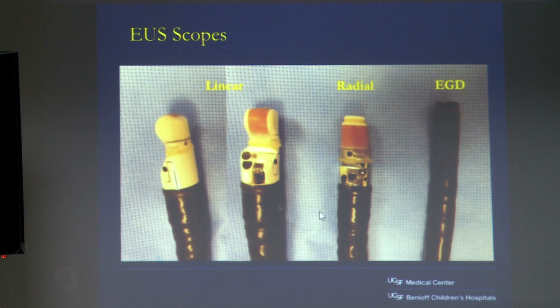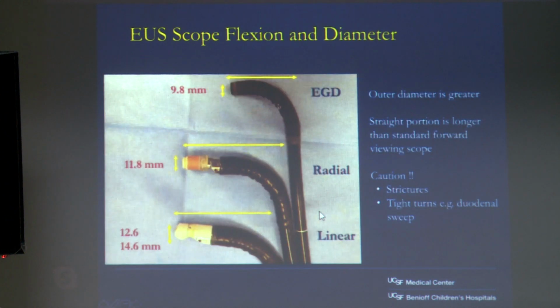And the other important factor is the bending angle of these scopes. So you have a 9.8 millimeter diameter scope for the upper. The radial is 11.8, and the linear actually widens to almost about 14.5 millimeters at its widest. And then the second important factor is that the straight part of the tip, once the scope is flexed, is much longer on the EUS scopes. So you're using a scope which is looking obliquely at 45 degrees, as Khalid mentioned earlier, and you're going through turns like the duodenal bulb. So just keeping in mind that you have a larger tip to navigate through the duodenal bulb and strictures.